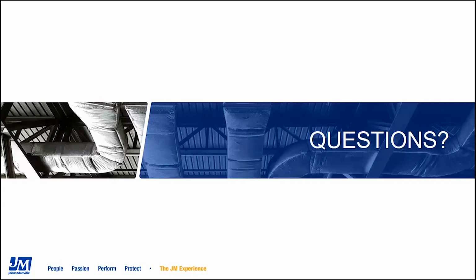Excellent. The next question is, what's the difference between installed R value and out-of-package R value? So I'm assuming that's tied to duct wrap. We get that question fairly regularly. Out-of-package R value is basically the thermal resistance to heat flow. If you were to take that duct wrap, open it up, lay it flat, and let that glass recover, the out-of-package R value is the uncompressed R value of that product. If you were just to lay it flat on the ground, let it recover, and test the thermal resistance of that product, that's the out-of-package R value.